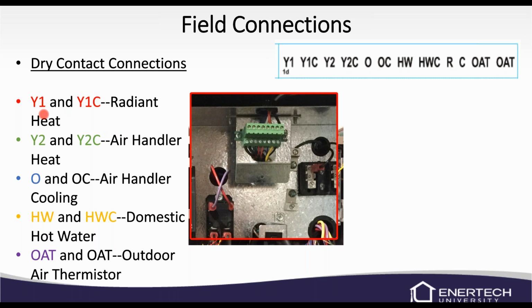So Y1 and Y1C, here on the terminal strip is how it's going to be labeled. If you were to take a jumper from Y1 and put it to Y2, there's no voltage to be measured here. Again, it's just contact closure. So if you put a jumper from Y1 to Y1C, you're going to have a radiant heat or a low temp heating call. If you were to jumper Y2 to Y2C, that'll give you a high heat air handler heating call.